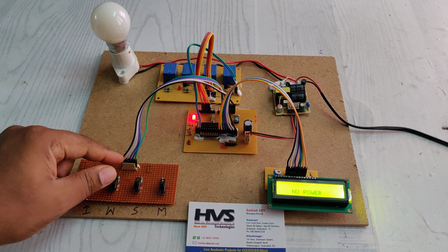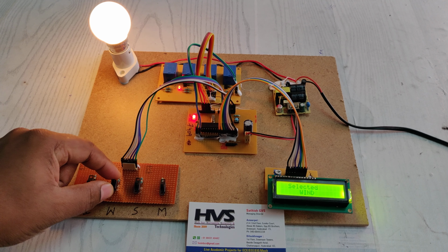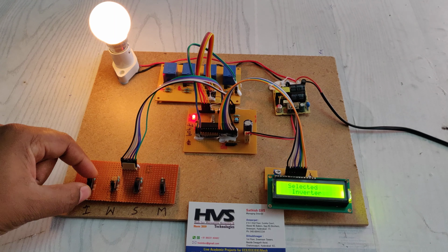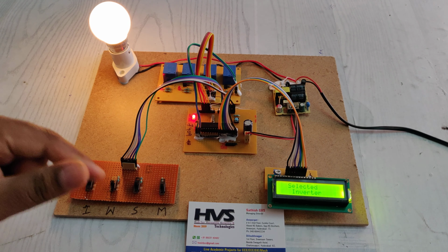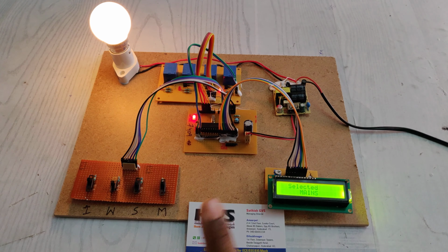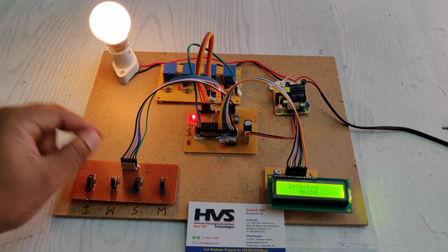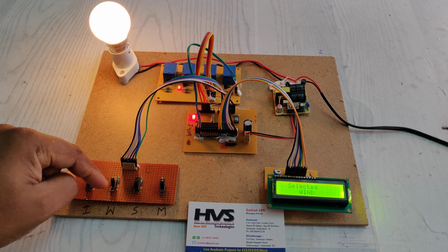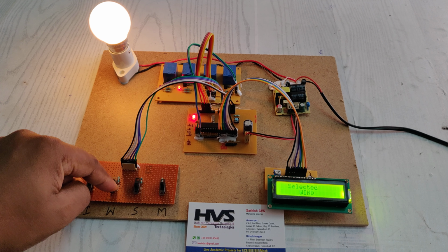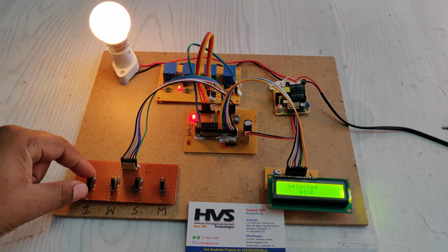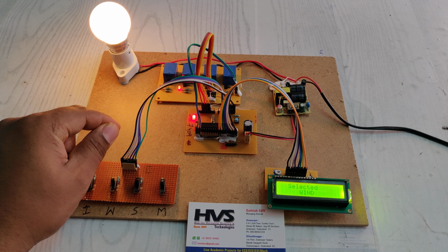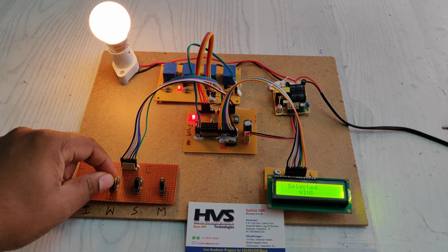In between, if any single source is available, it will switch to that source irrespective of priority, as only one source is available. See now, the inverter. Once the inverter is there, and then the mains comes, it will directly go to the mains. If then the wind comes, it will go to the wind. If the solar comes also, it doesn't matter, because in the priority based scheme we provided the highest priority to the wind, as it is low cost. See now, the inverter is gone, and even though it is available, it won't switch to the inverter circuit. If the mains is also available, there is no switching to that, only the wind, which is the highest priority case.